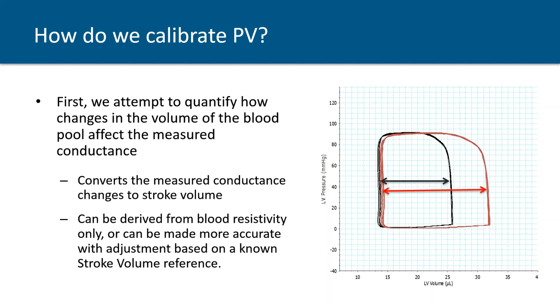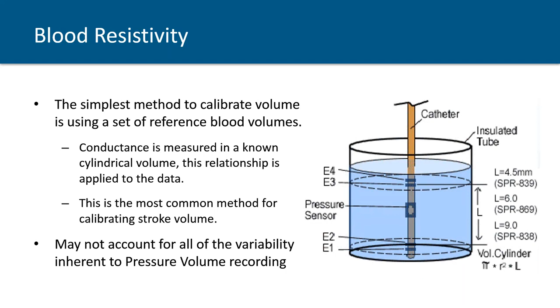So the first method that we discussed was that of blood resistivity, or the cuvette methodology, which is the simplest method of all the techniques. It's using a series of wells or cuvettes of known volume with a solution of known resistivity, which ideally matches blood resistivity. The conductance catheter is placed in the center of each cuvette, and subsequently you can construct a conductance versus known volume curve for each of the volumes.